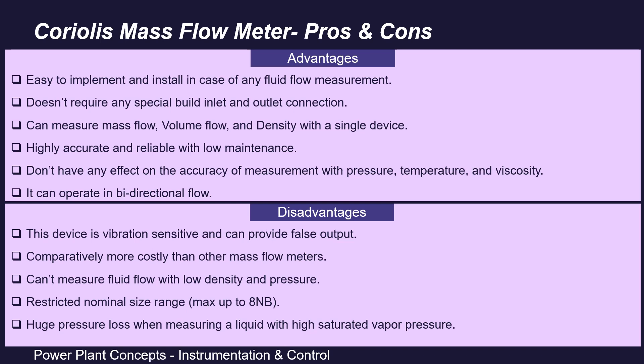Coming to its advantages and disadvantages: advantages of using a Coriolis mass flow meter include that it is easier to implement and install for any fluids, it does not require any special inlet and outlet connections, and it can measure mass flow, volume flow, and density with a single device. It is highly accurate and reliable with low maintenance, and has no effect on measurement accuracy from pressure, temperature, or viscosity changes. It can also operate in bi-directional flow and has a self-draining facility.